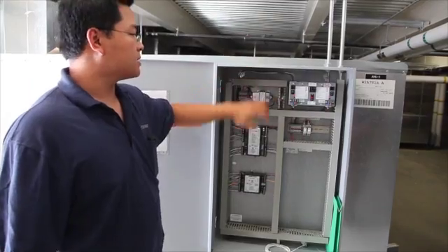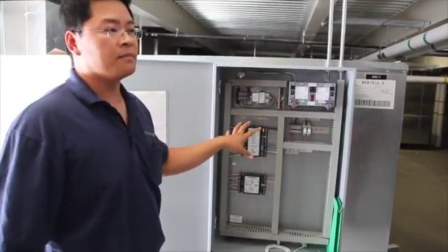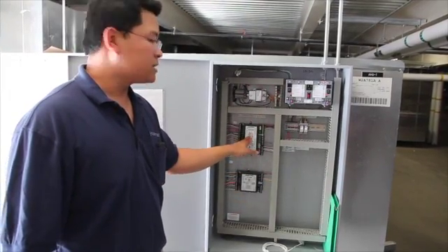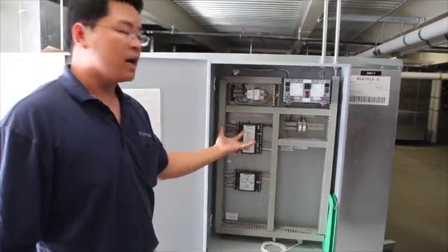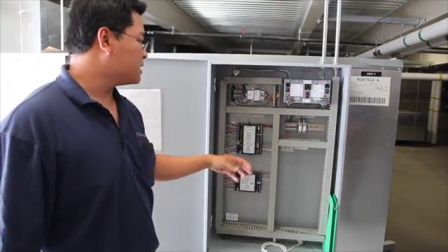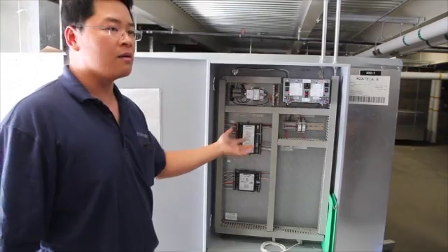All the units around here, Air Handler 1, has a similar setup. Exact same controller as well. Input and outputs. These controllers, once they go bad, if it's not lit up for any reason, it's not commanding the units on, they can be swapped easily. Just get a new controller, swap in, download the code.